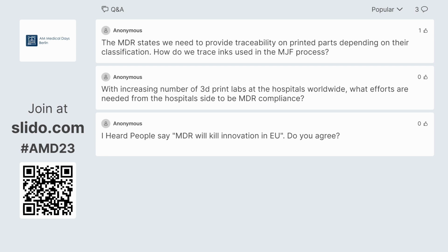Bernhard mentioned it, but Erik, can you please remind me what we call a point of care solution, and which devices should benefit from a quality check process and which do not? Well, I think the MDR speaks about an in-house manufactured device, where it's made within the health institution, and it also says that the MDR does not apply, more or less, except for Annex 1, the general safety and performance requirements, provided that some conditions are met. Some of these conditions are that it has to stay within the health institution; you can't give it to other hospitals. You also have to do it under an appropriate quality management system. So these kinds of restrictions are there, but it also gives quite a lot of freedom, I would say.